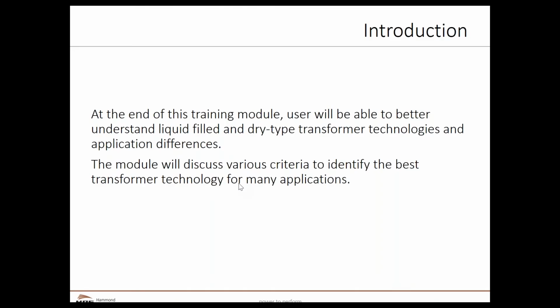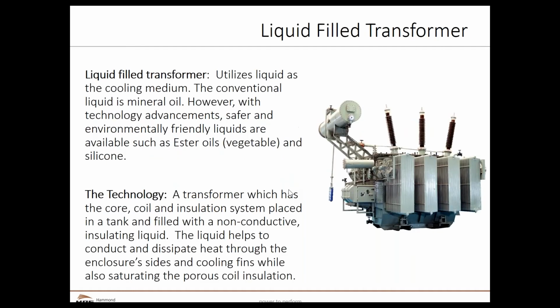At the end of this presentation, we're hoping that everybody has a good appreciation for the differences between both dry type and liquid type technologies. So let's start off with liquid filled transformers. They are called liquid filled because that is exactly what they are. We build a transformer, and if you compare the core and coils between a liquid and dry type, they're very similar. If you put up either a dry type core and coil or a liquid core and coil, you will recognize it as a core and coil, although there are some construction differences we'll talk about.